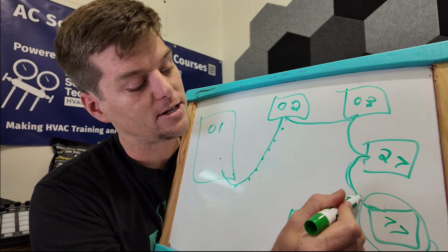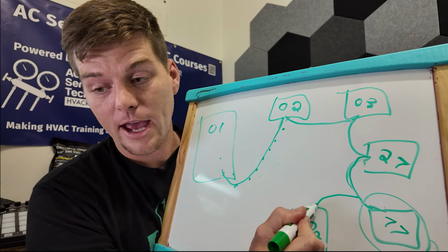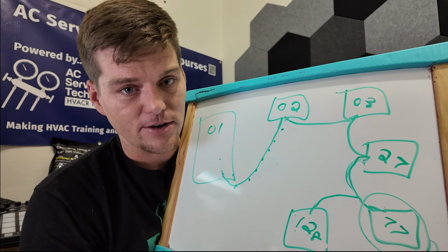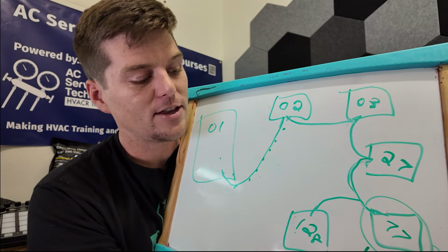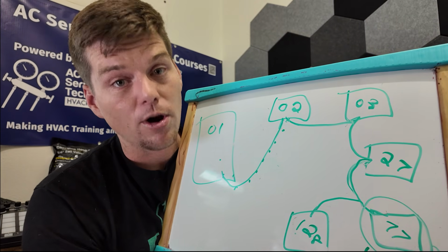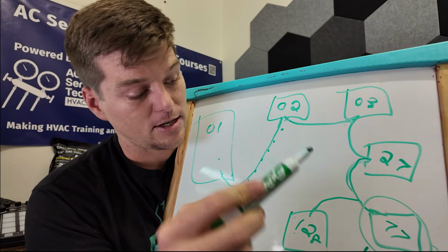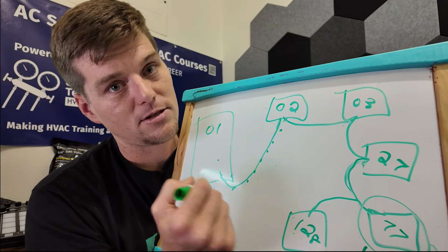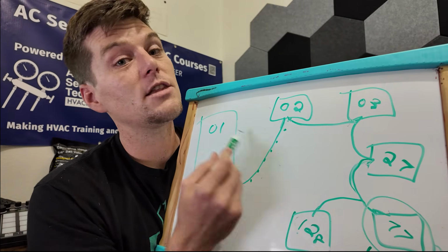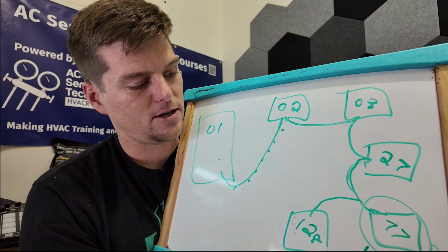I can even go further, is to just take the wires off, wire nut them together, and put 128 back in the series. Does this work? Because if this works, then I know 100% that 17's got a bad A1P board, or there's something wrong with the communication within that system itself, and I can troubleshoot that alone while I get the rest of the system back up and running. This is the process for troubleshooting this network.